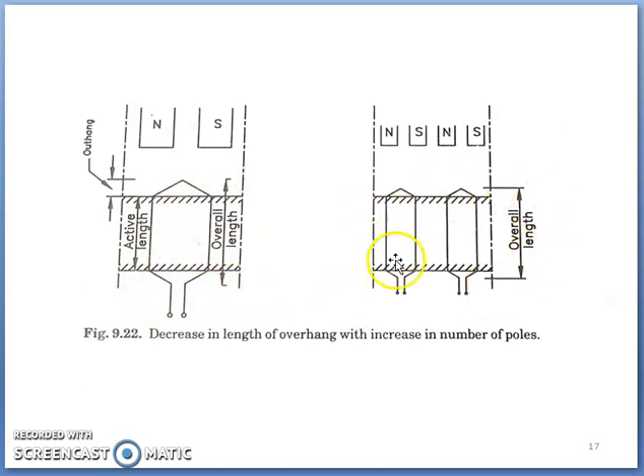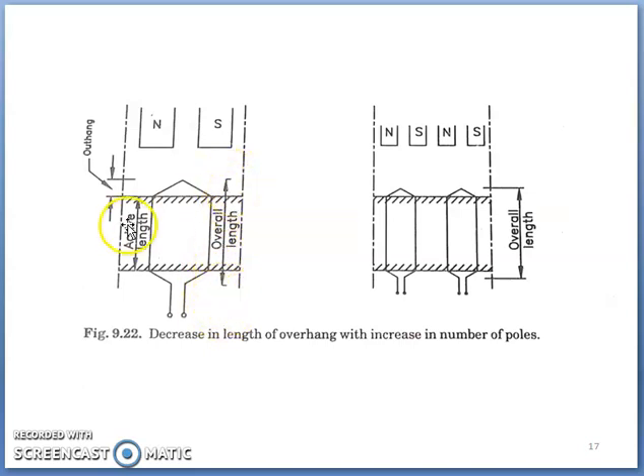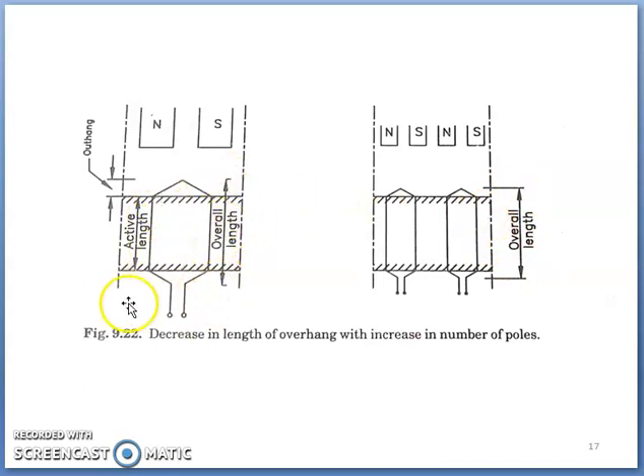This is for a two-pole machine and this image shows a four-pole machine. In the case of a two-pole machine, the length of inactive copper is more compared to that of a four-pole machine. Depending upon the length and number of overhangs and the number of poles, the overhang length of the machine will change. Whenever the number of poles is less, the overhang will be more. The overall length depends upon the active length of conductor embedded in the slot and the overhang.